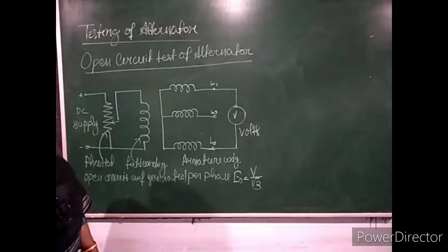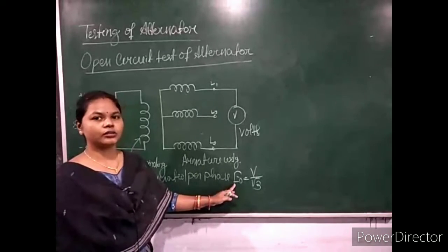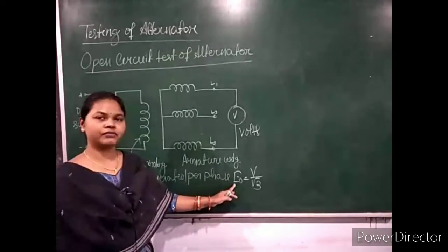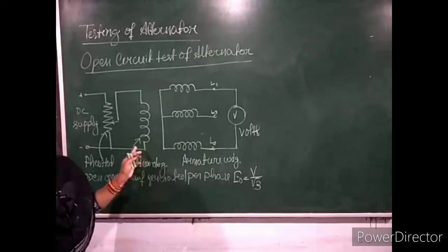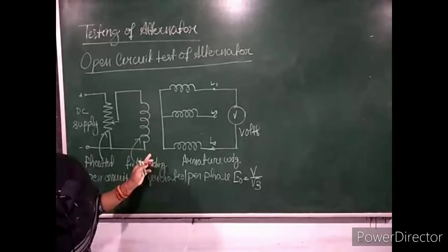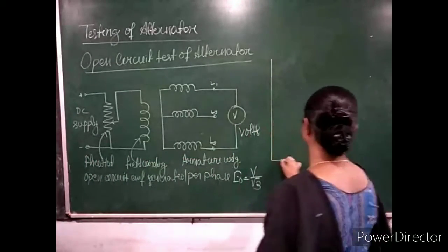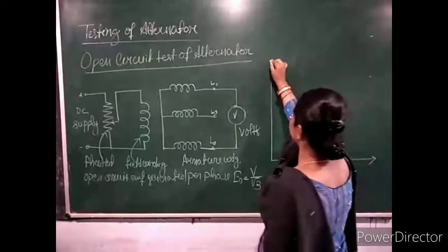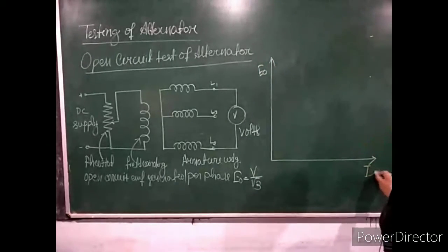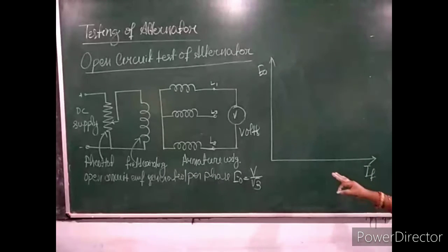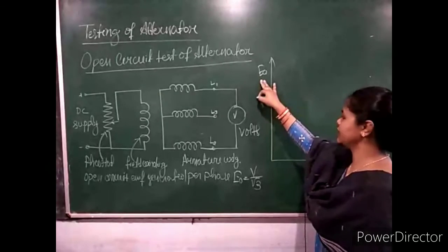Now, after getting this value, you draw E0, that is the open circuit voltage per phase, against the field current, and study their characteristic curve. Here I drew the nature of the curve, E0 versus IF. It shows how the open circuit voltage per phase increases with increase in field current.